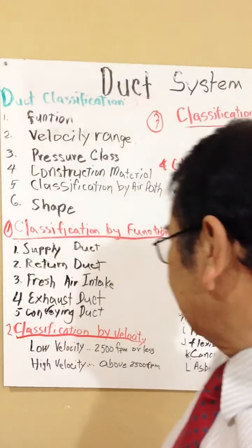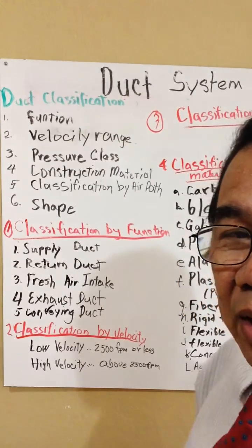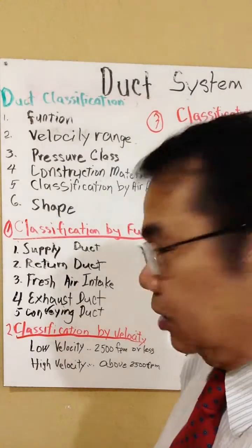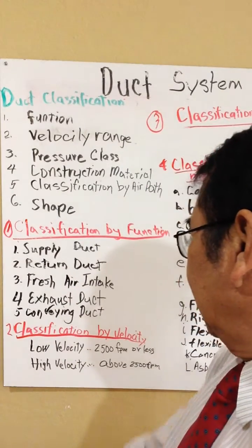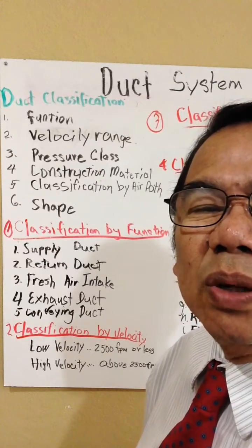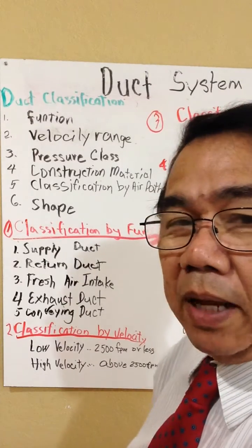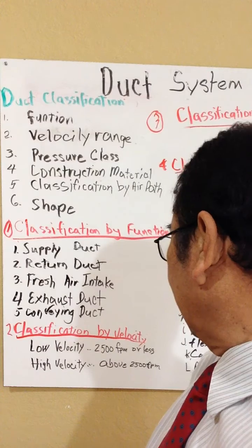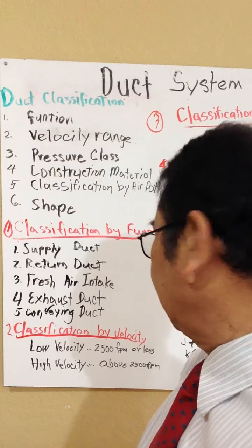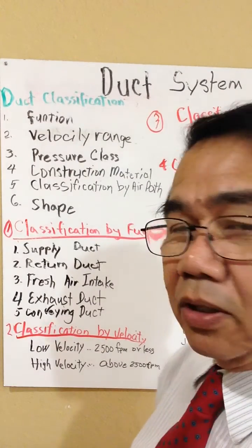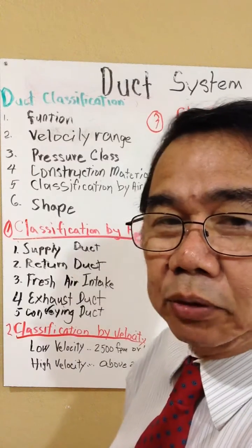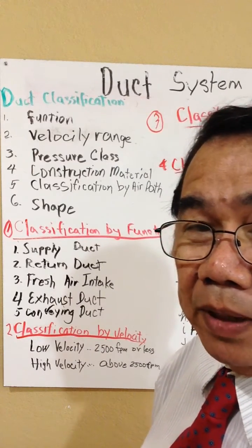The second classification we're going to discuss is classification by velocity. We can classify ducts as low velocity, meaning 2500 fpm or less, and high velocity, which is above 2500 fpm.